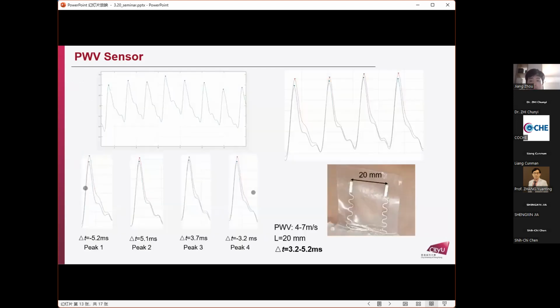Here is some of the data we acquired from the laboratory. This is a small prototype we made for some little testing, and these are several complete pulse wave cycles from our device. We can see there's a little bit of a shift to the right for the second pulse wave. The pulse transit time varies from 3.2 milliseconds to 5.2 milliseconds. The distance between the two pressure sensors is 20 millimeters. Then we can get a pulse wave velocity of around 4 to 7 meters per second.